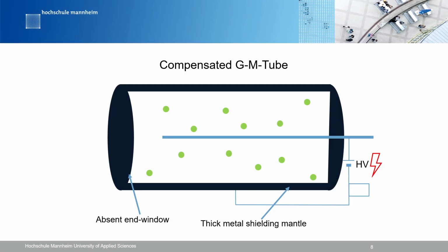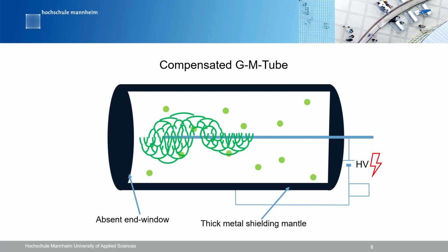The fundamental reason for those differences lies in the design. Officially calibrated dose rate meters use energy-compensated Geiger-Müller tubes, contrasting with the end window design of the Gamma Scout, leading to different calibration methods. The Gamma Scout is calibrated specifically for cesium-137, whereas energy-compensated GM tubes can determine dose rates for various nuclides. However, it is worth noting that such devices also come with a considerably higher cost attached.